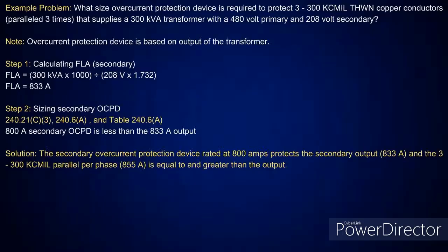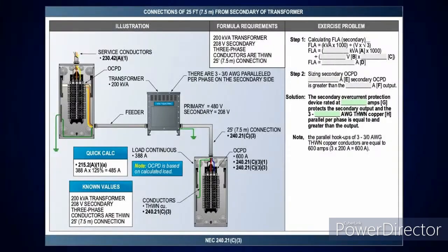Now, the next one, same thing, C3. If you notice, I've got a 300 kVA transformer. Once again, that secondary is 208 volt. I did the exact same calculation, and I came up where I could put an 800 amp overcurrent device there. All of this is very, very simple. A lot of people don't realize, when they see 833 amps in their calculation, that you can drop down to the next standard size.